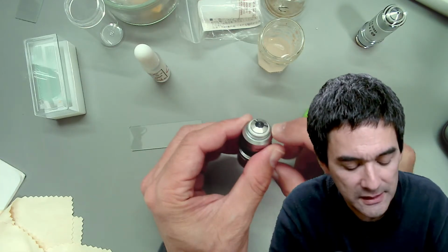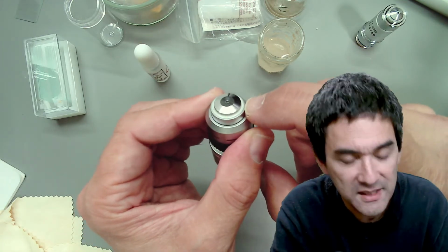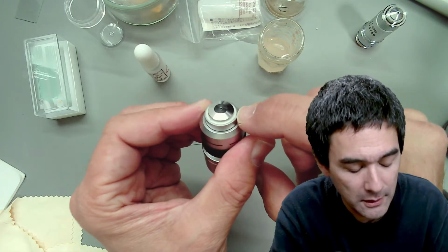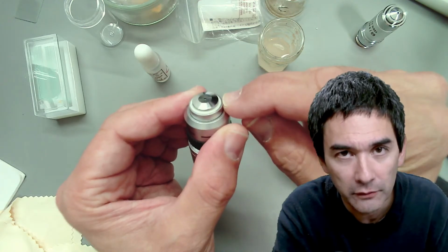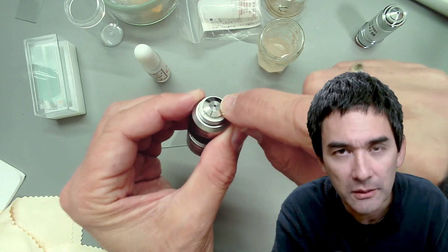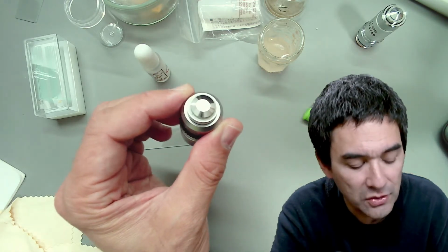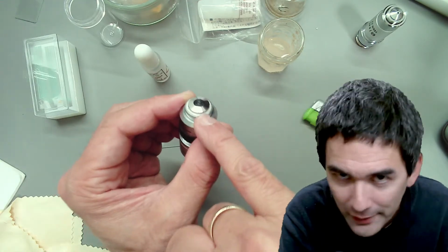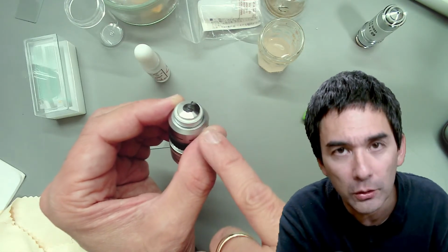Look over here. This here is an oil immersion lens. Do you see the white ring here? I don't know if you're able to see this. This seems to be some kind of cement, plastic, or rubber maybe, and has been applied here to seal it off so that no oil can go in. Now if you use an improper solvent, you might actually damage these things, or sometimes the lenses are also glued in place. So what you generally want to do is prevent any liquid flowing into the lens, of course not the oil, and of course not any cleaning solvent. And the solvent that you use should be very volatile.